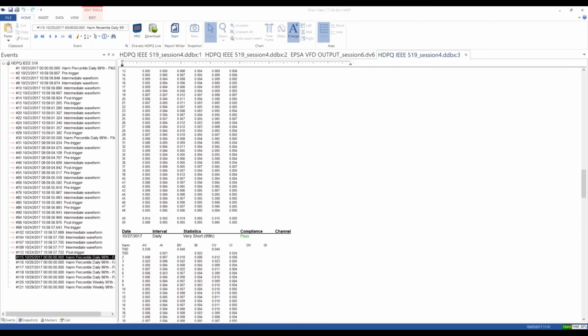And then yes, that information is entered from the screen that I showed you, where you would enter what we call the max demand current and the max short circuit current. And then the instrument has what it needs, because remember, your TDD limits are basically set based upon that ratio, which is the short circuit current to max demand current. So yeah, that information you would need to have. Usually it's supplied by the utility, and then the second answer is yes, that information is entered into the instrument during the setup.